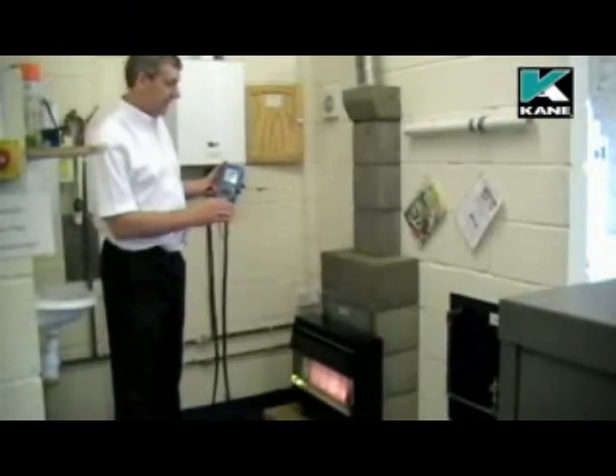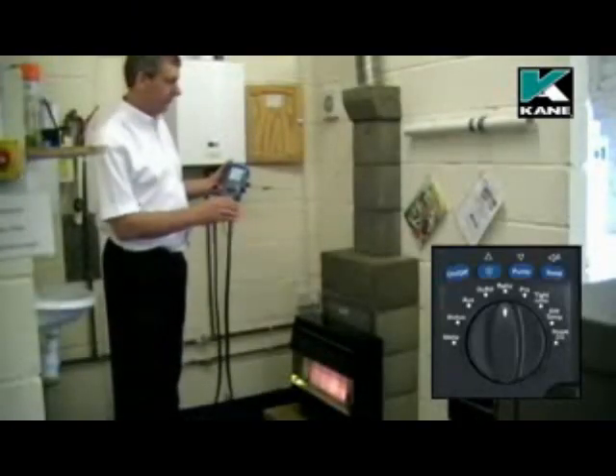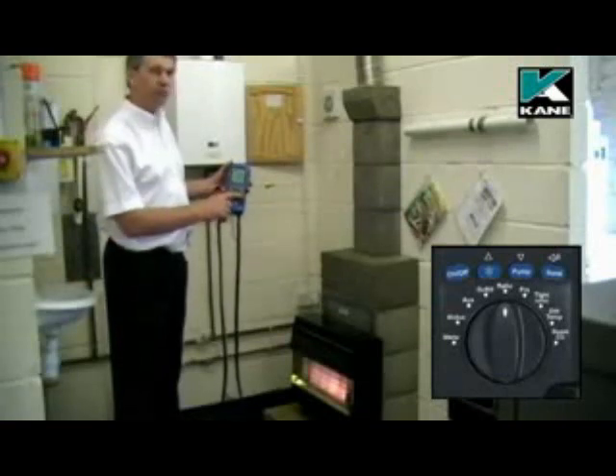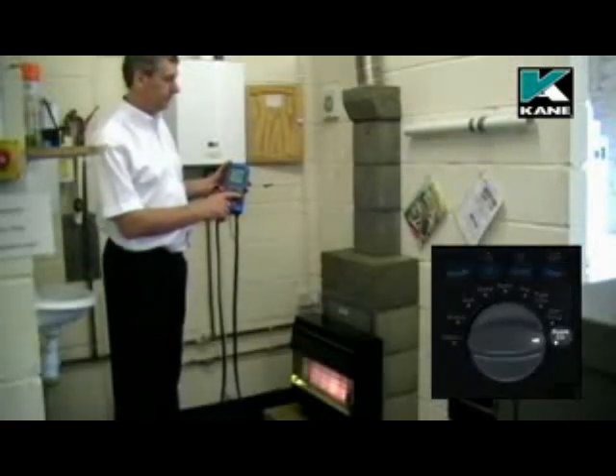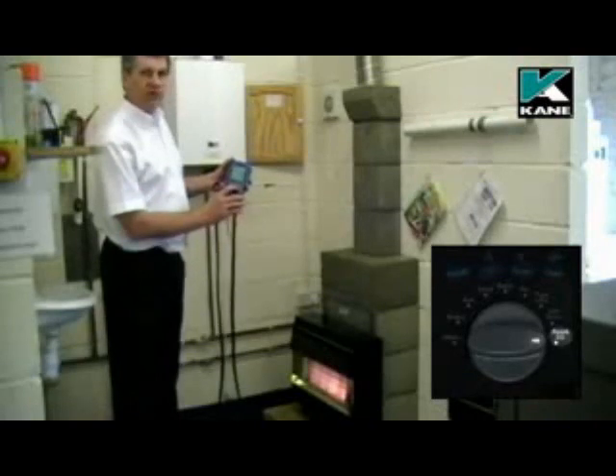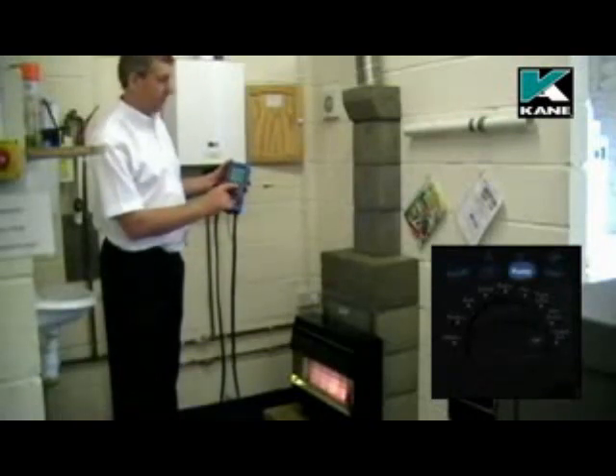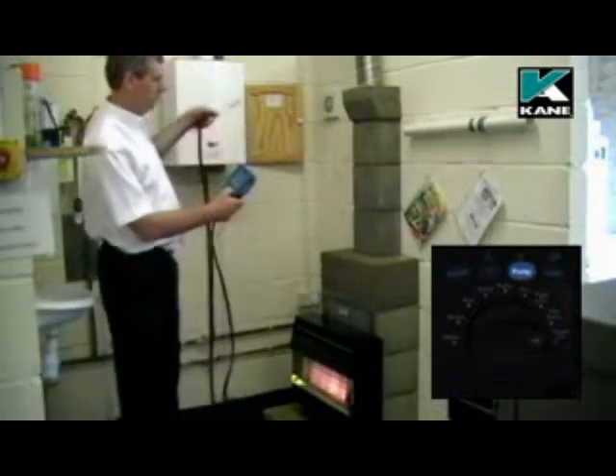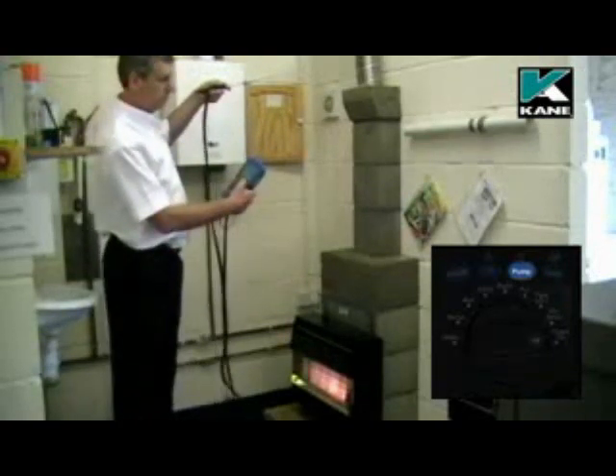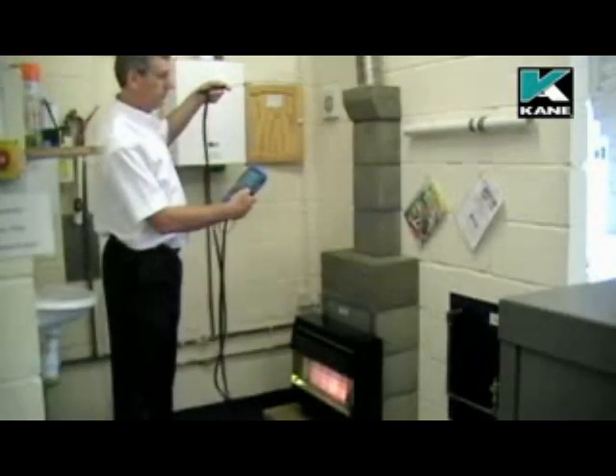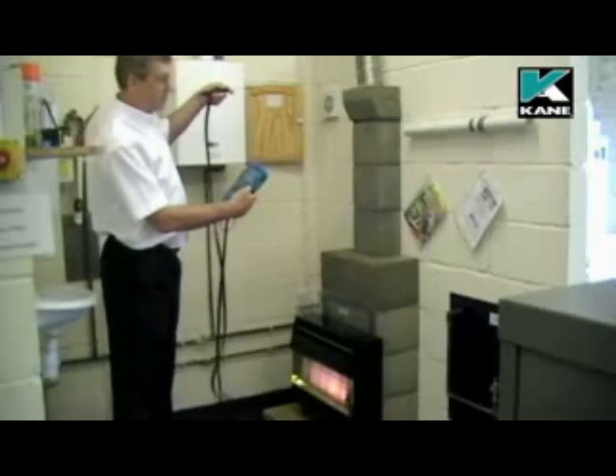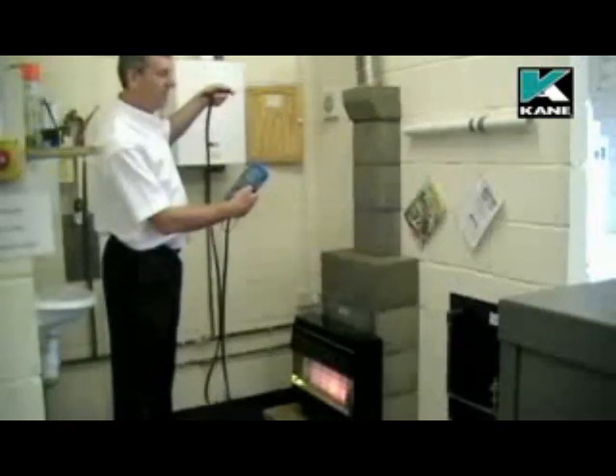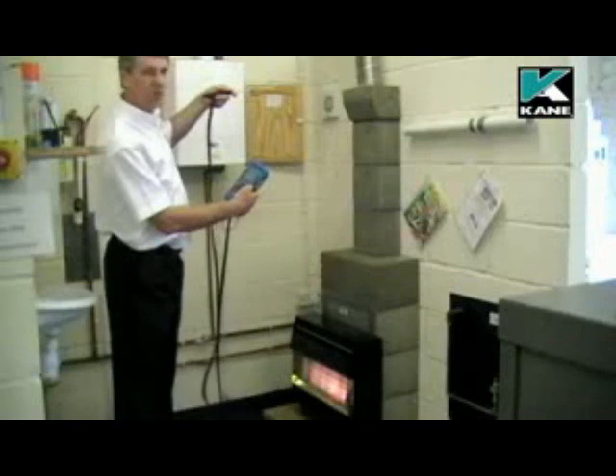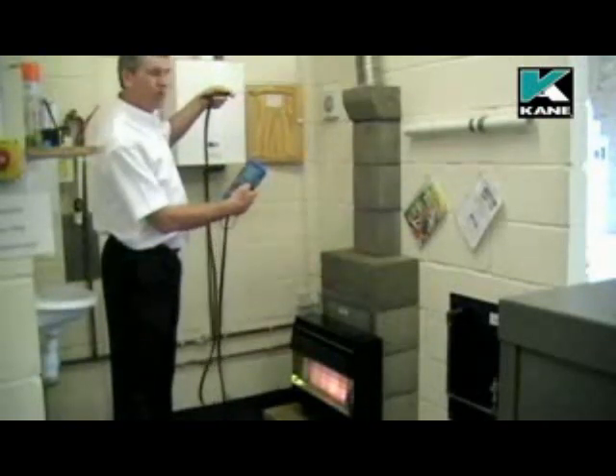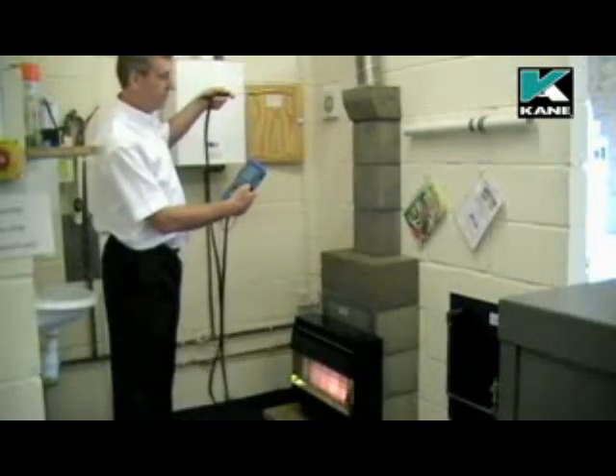To test ambient CO levels, move the dial to the room CO position. When you want to start the test, press the pump button. The pump starts and the analyzer continuously measures CO. It records the highest CO level that it's seen during each minute.